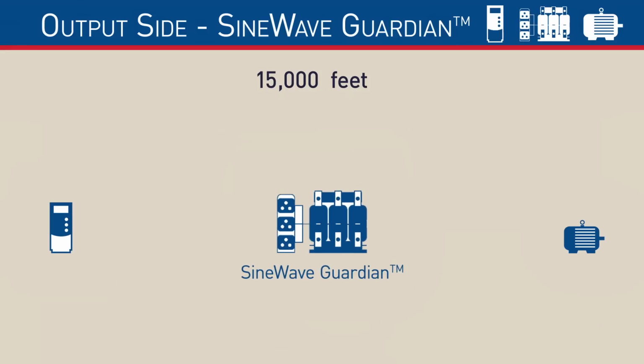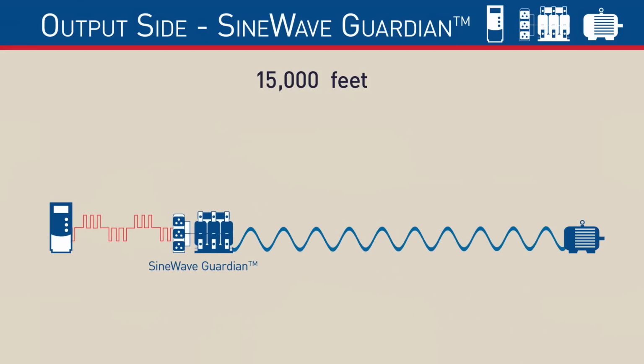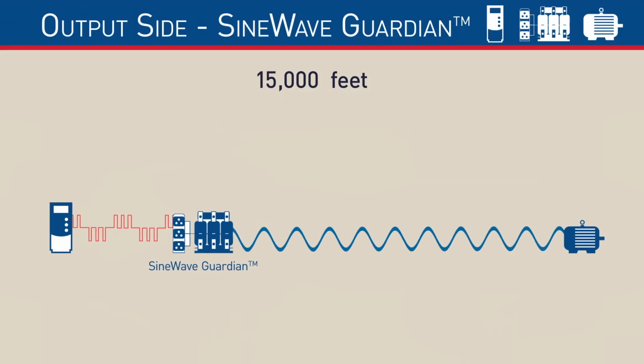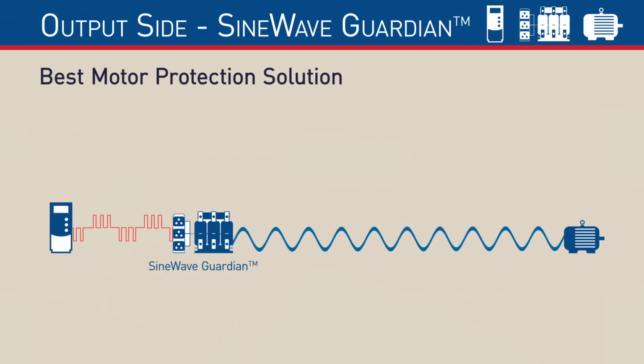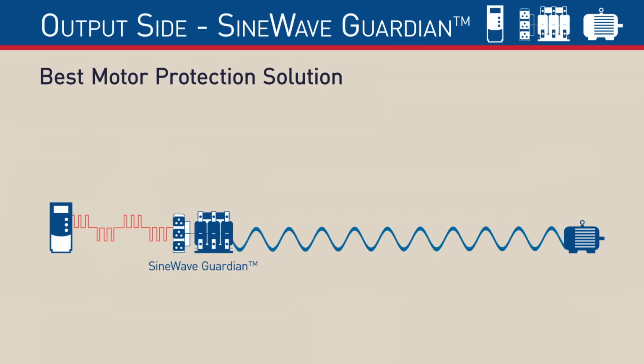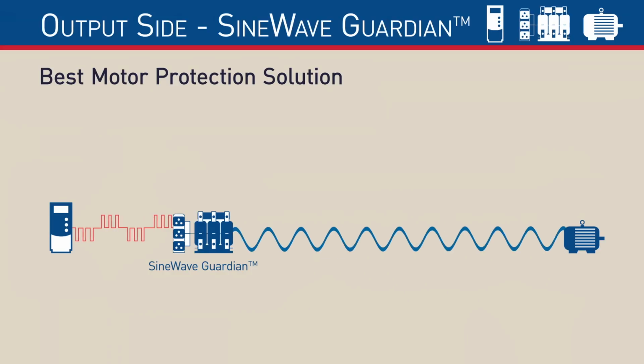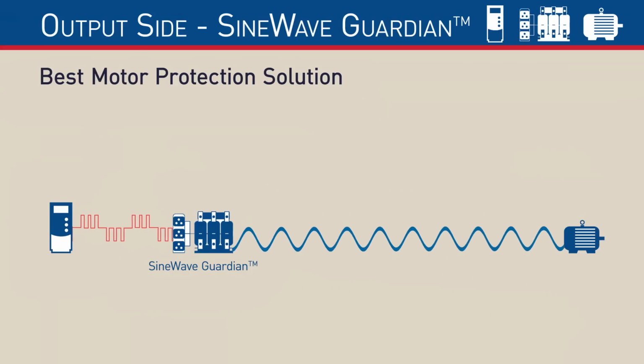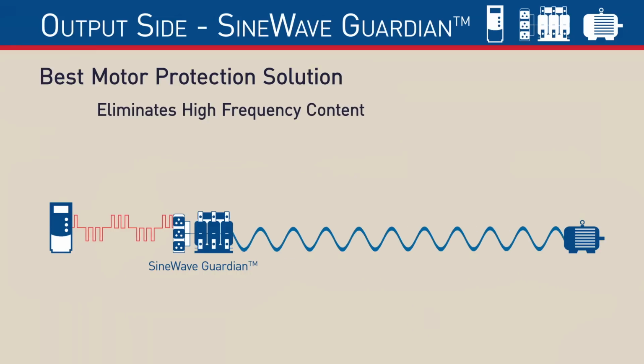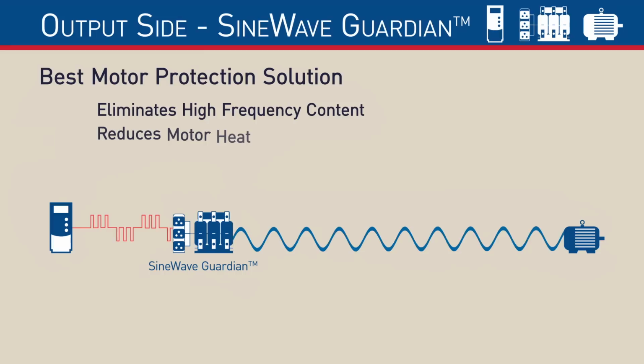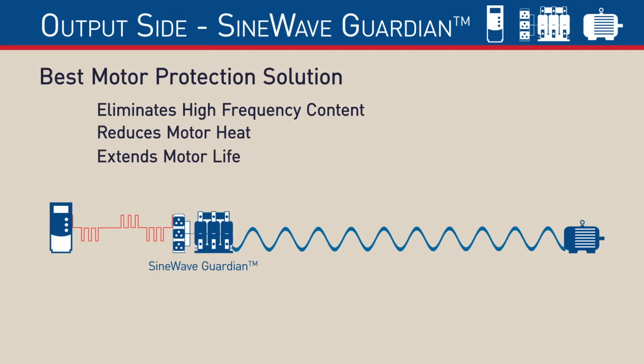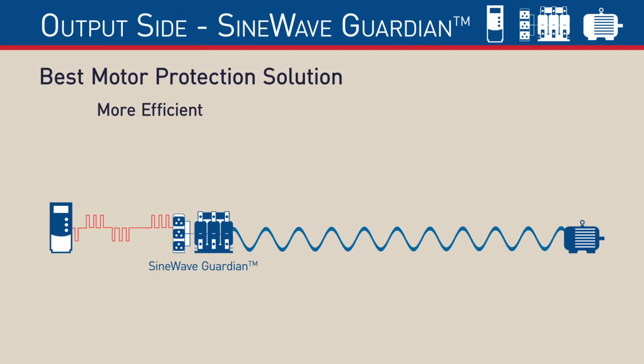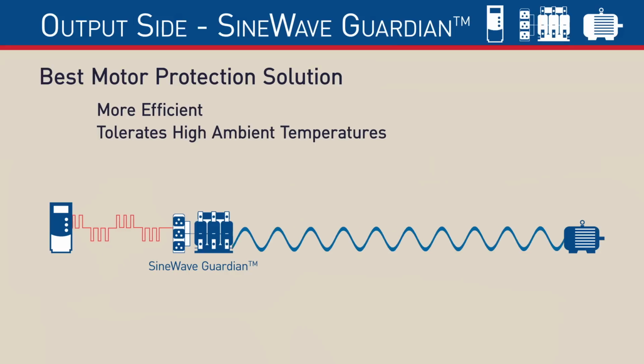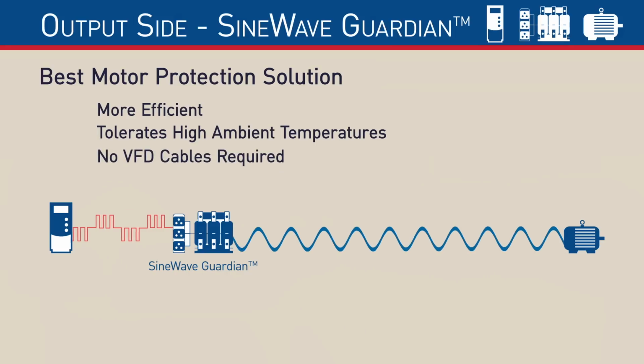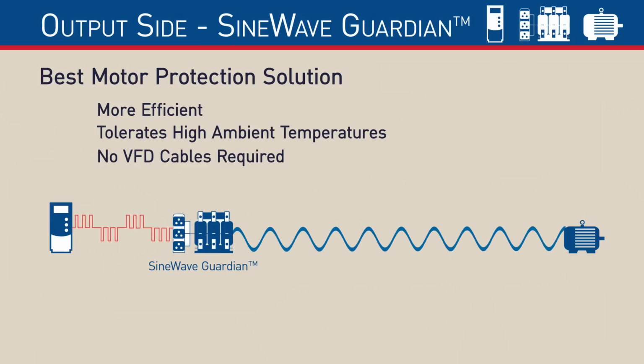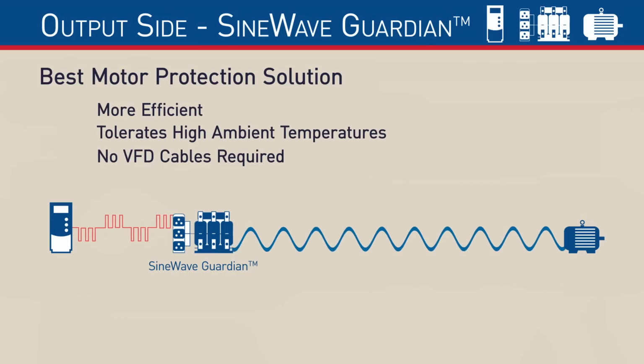MTE's Sine Wave Guardian filter allows us to run a motor at any cable length up to 15,000 feet. It is the best solution on the market today for motor protection in that it cleans PWM waveforms generated from the drive by virtually eliminating high-frequency content and voltage peaks, as well as reducing motor heat to give customers extended motor life and less downtime. It's more efficient, tolerates higher ambient temperatures, and doesn't require VFD cables, making it ideal for a variety of applications from steel mills to oil fields.